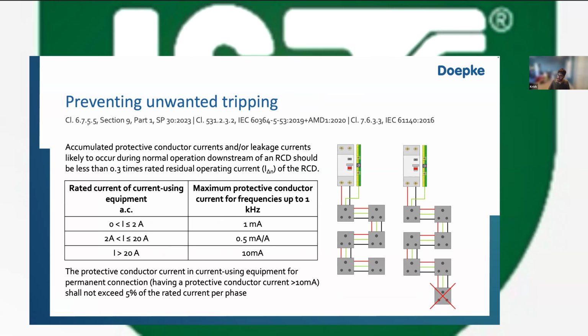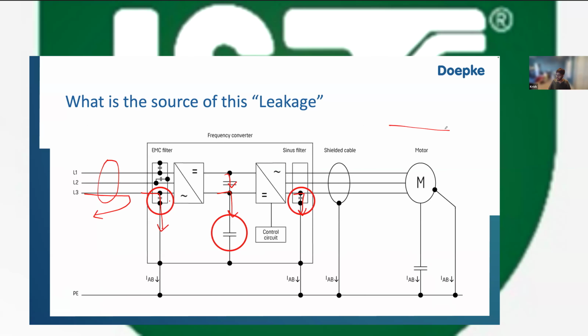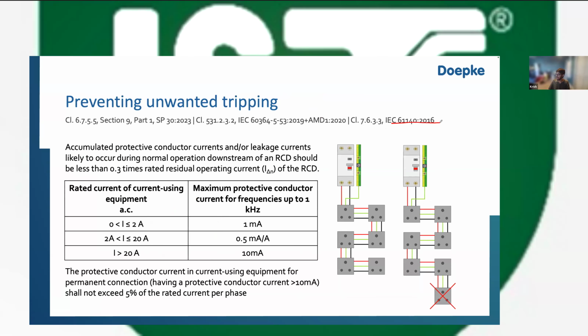How much current is this? You see IEC 61140, which is the standard here. It talks about how much protective conductor current is permissible for equipment, including variable frequency drives. It mentions that the amount of current that is allowed to leak depends on the rating of the equipment itself. If you have a device between 0 and 2 amperes, you are allowed 1 milliampere. Between 2 amperes and 20 amperes rated current, you are allowed 0.5 milliampere per ampere. For example, for 15 amperes, you have 15 times 0.5 milliampere per ampere, so 7.5 milliampere. And if you exceed 20 amperes, you're allowed 10 milliamperes max.